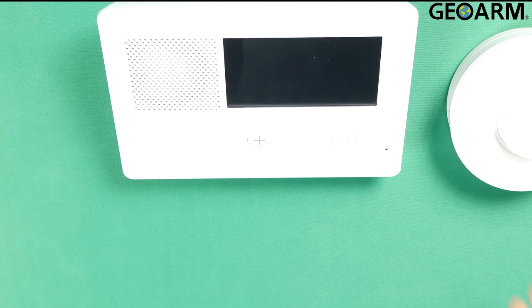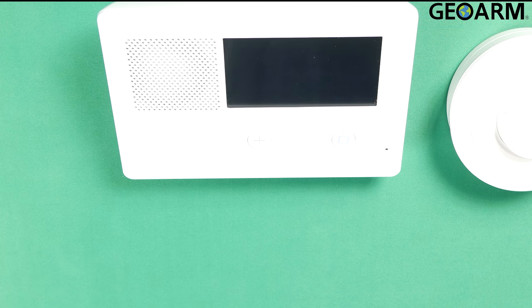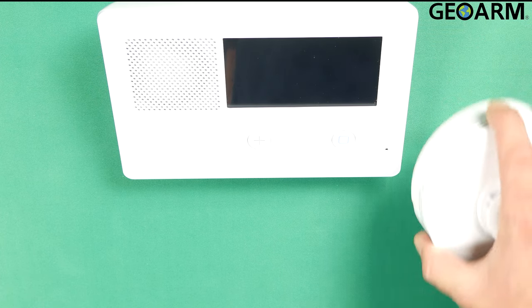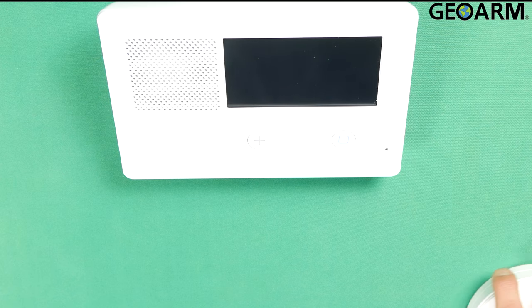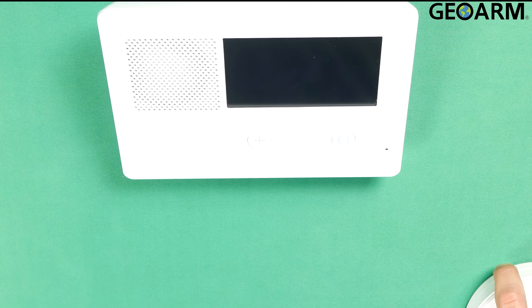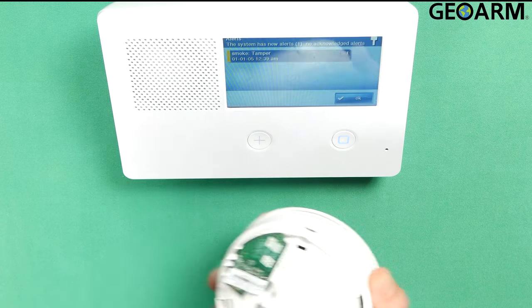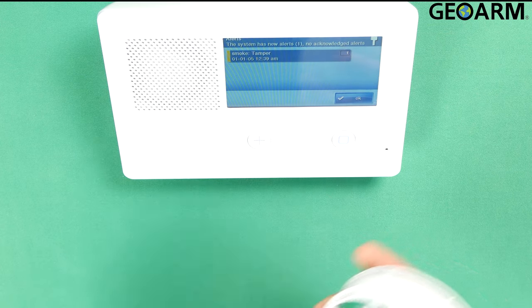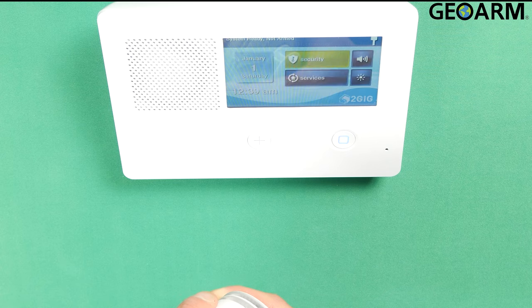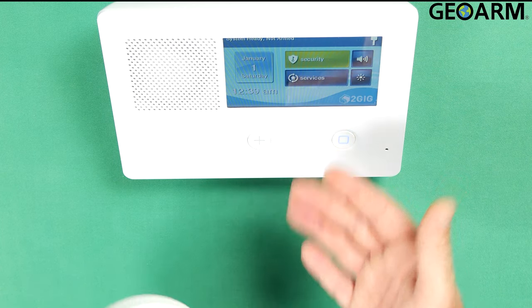Now at this point it should go into a reboot procedure. That's perfectly normal. It's going to cycle and then once it comes back up and the screen comes back I should be able to tamper this device and you'll see it appear on the screen as smoke. So let's give it a minute here. All right now we'll tamper this device. See so we got smoke tamper now. So it is monitoring that for supervision. I put the cover back on and it goes away.